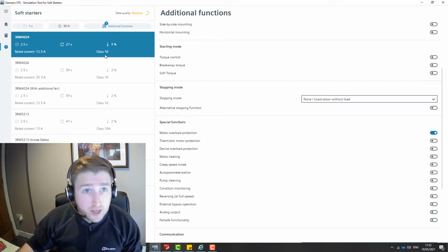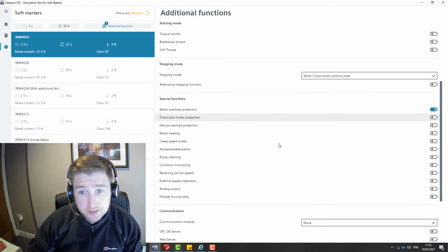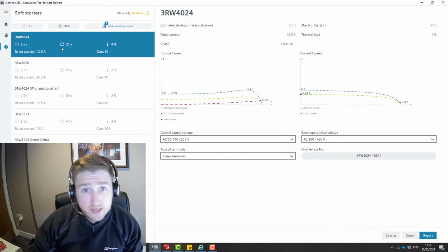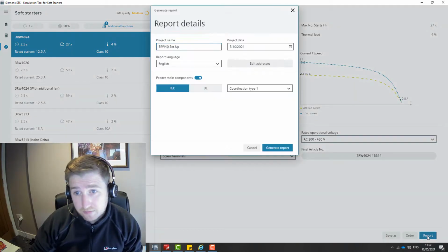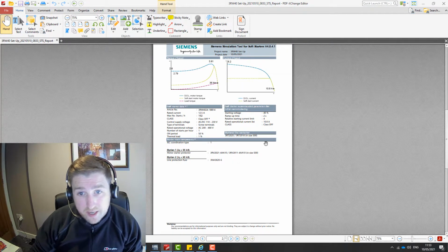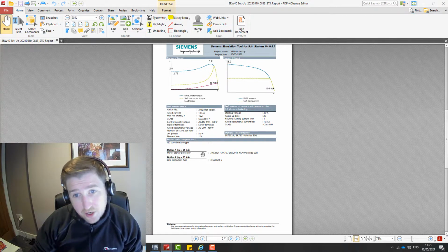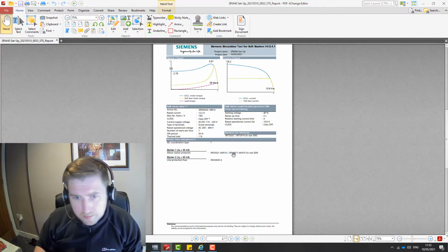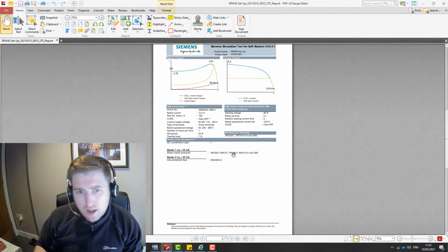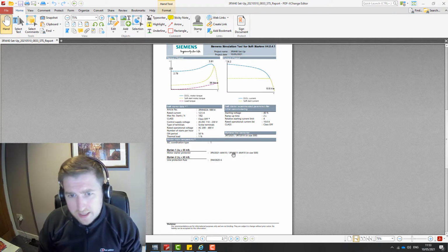And once you've done that, you can take a look at the report which has been generated afterwards. Once you've selected the suitable soft starter, you can go into report, have a look at the coordination, and you can get the short circuit protection added in here, and then you can go and generate a report. And what you get from that, as you can see here, is suggestions for the short circuit protection, which is great because all these combinations have been tested to the latest IEC regulations.